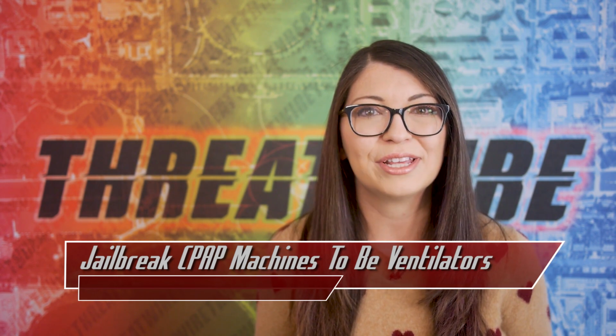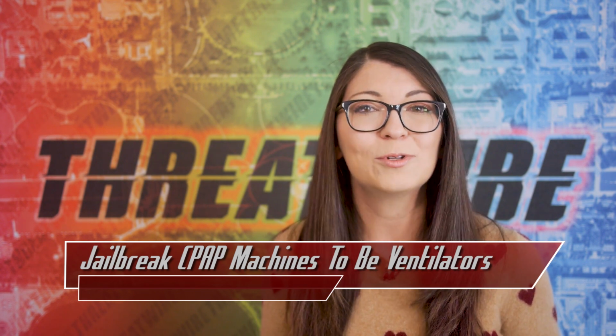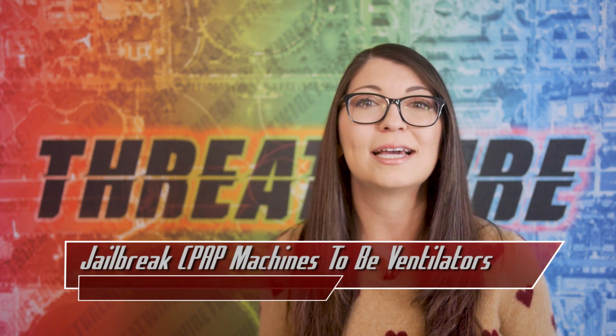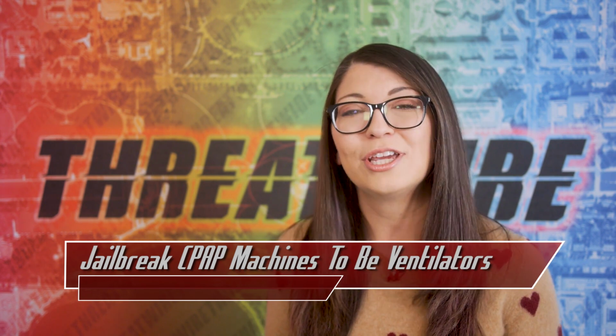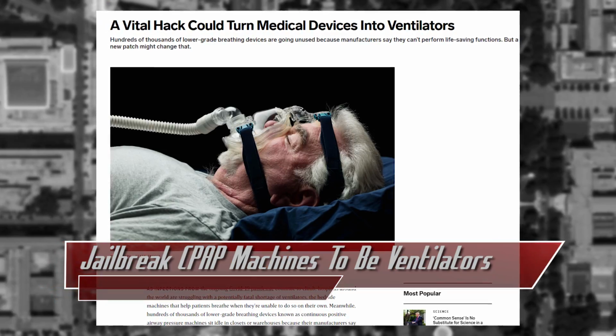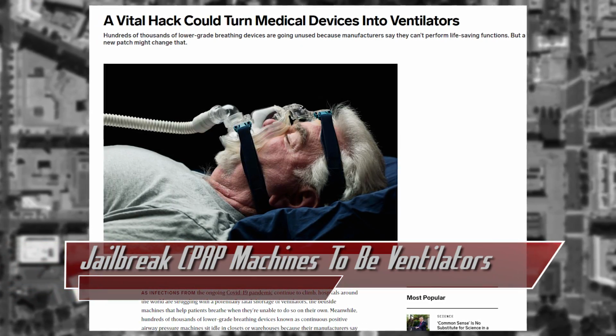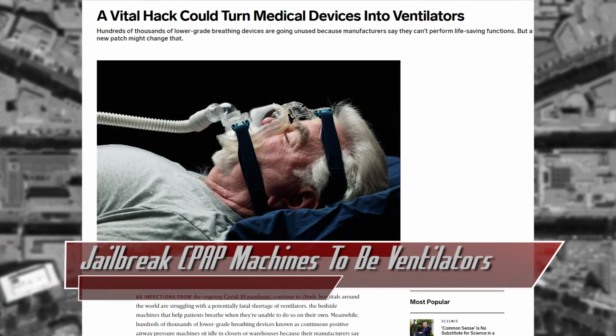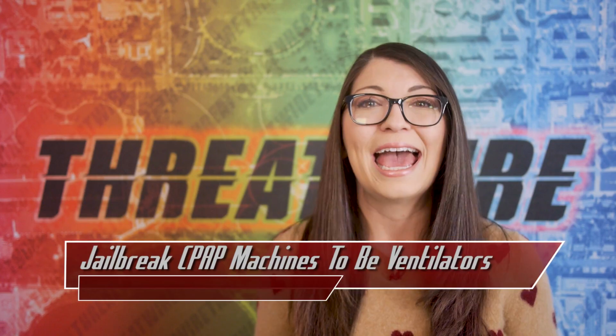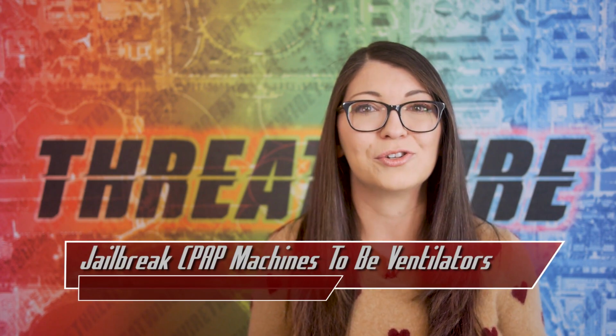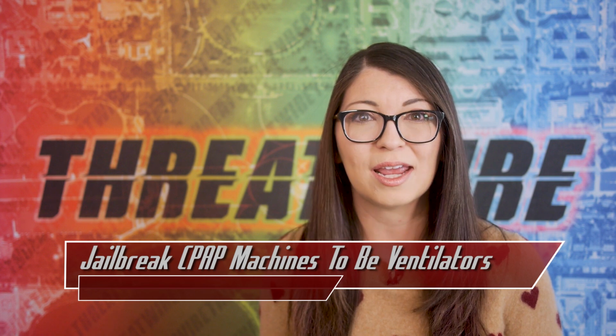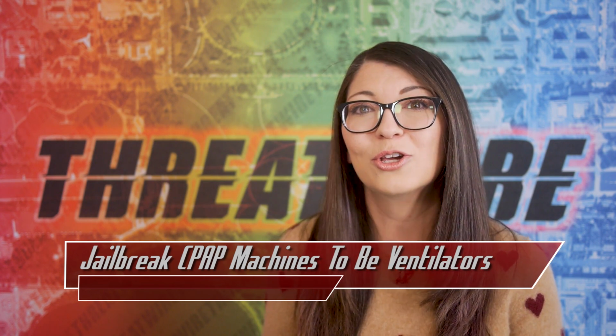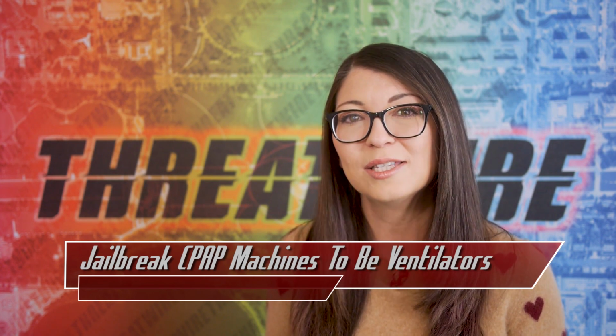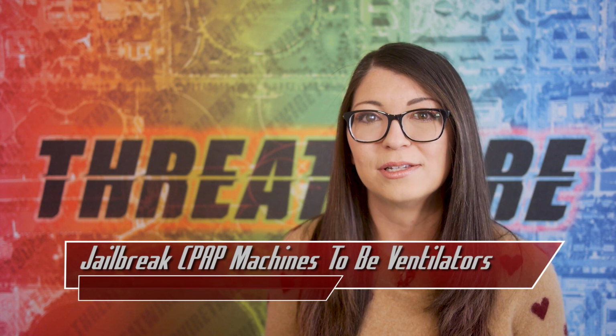After reverse engineering the AirSense 10, Hudson was able to demonstrate using this machine as a bi-level device with a patch he calls Airbreak. Now, since the FDA has approved BiPAP machines to be used as ventilators during this pandemic, as long as they are fitted with filters to prevent the virus from spreading, this means that his jailbreak could put even more devices into hospitals to combat the virus.